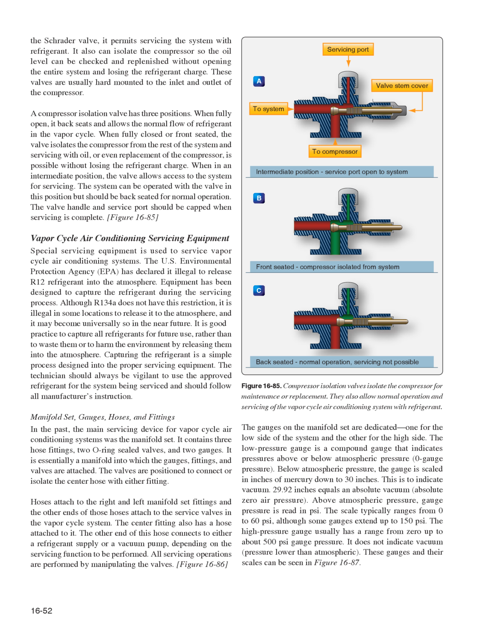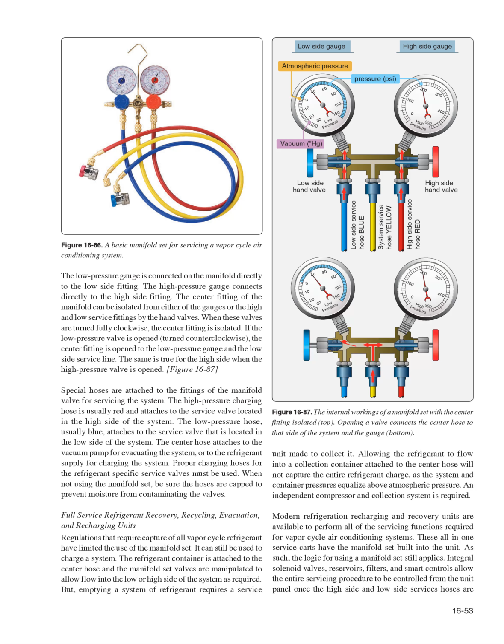The scale typically ranges from 0 to 60 pounds per square inch, although some gauges extend up to 150 pounds per square inch. The high pressure gauge usually has a range from 0 up to about 500 pounds per square inch gauge pressure. It does not indicate vacuum, pressure lower than atmospheric. These gauges and their scales can be seen in Figure 16-87. The low pressure gauge is connected on the manifold directly to the low side fitting. The high pressure gauge connects directly to the high side fitting. The center fitting of the manifold can be isolated from either of the gauges or the high and low service fittings by the hand valves.